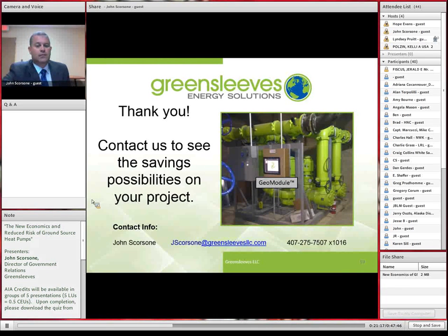All right, next question: are the bore fields spaced differently when using this type of system? No, the bore fields are typically about 20 feet on center — we don't adjust bore field spacing, we use traditional spacing. Our company is quite capable of being the designer of record on a bore field, and we're happy to partner and advise others. The important thing to add is that net land area used is smaller, because if you're putting in fewer bores, the land area you impact is a lot smaller.